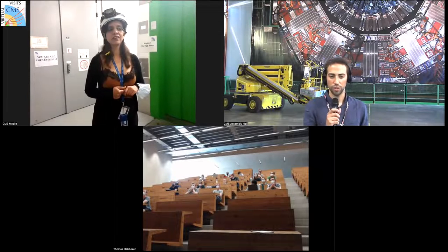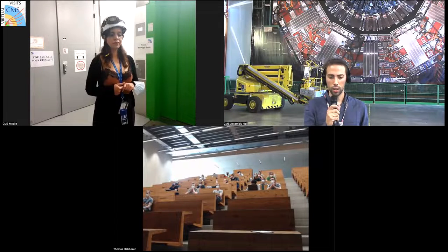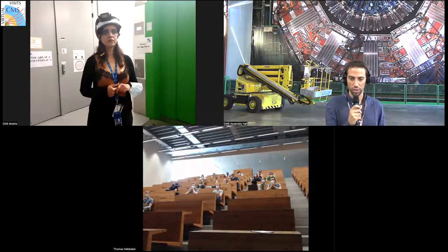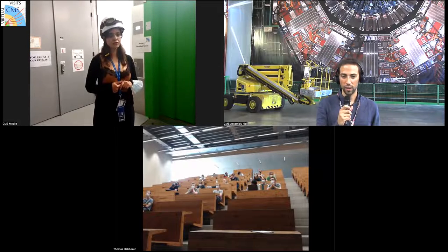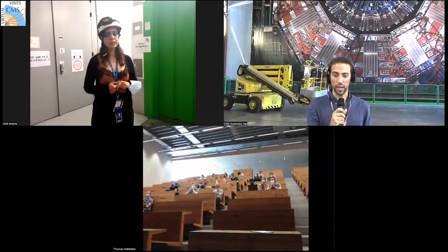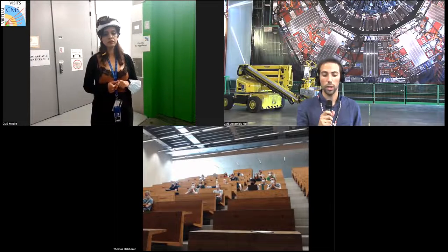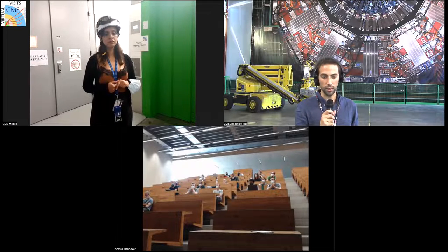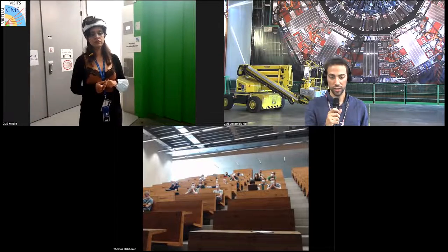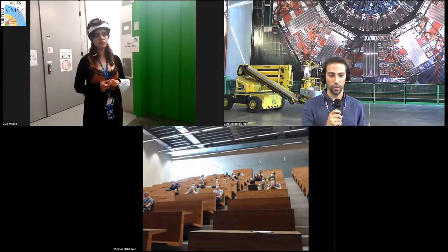There was also another question for services, if they stay connected during the technical shutdowns, for example. I can comment for GEMs. Well, GEMs was just installed, so we didn't really see a big shutdown. But yes, I think the answer is yes. We keep the HV connected, the low voltage. So HV stands for high voltage, low voltage connected all the time, and the gas system as well, and the cooling as well. You go and disconnect services in case of a problem. I think that's the main line. I don't know if DTs do it in a different way.